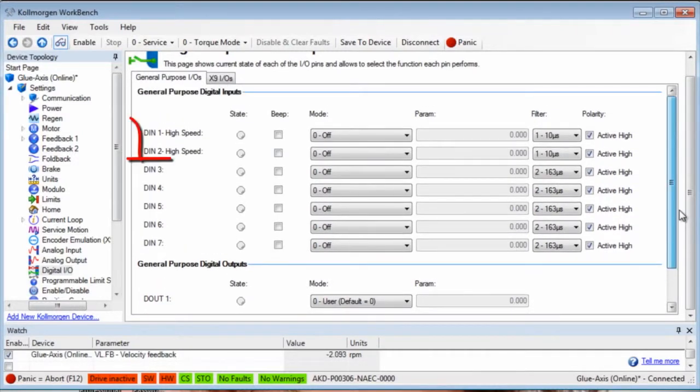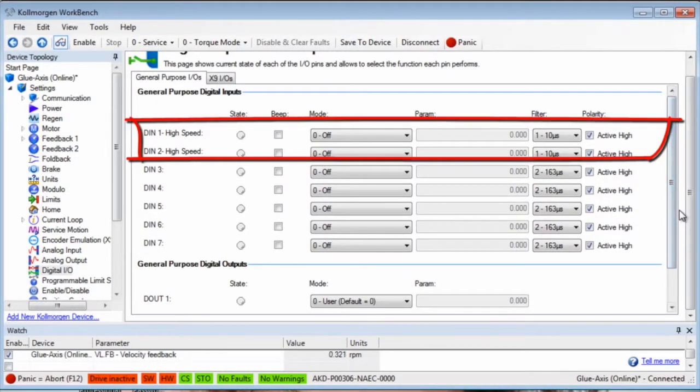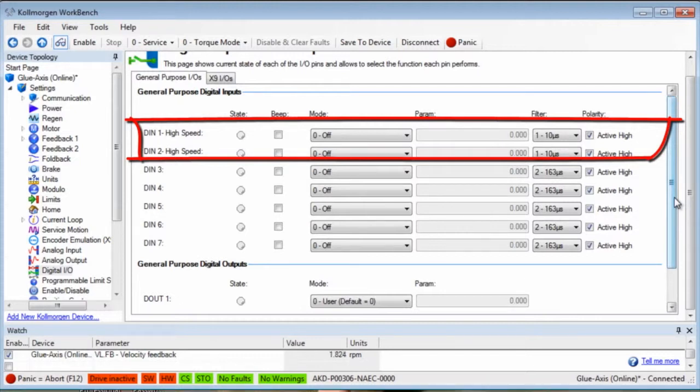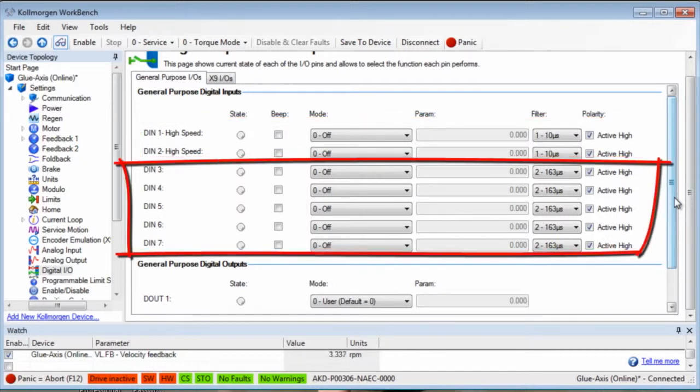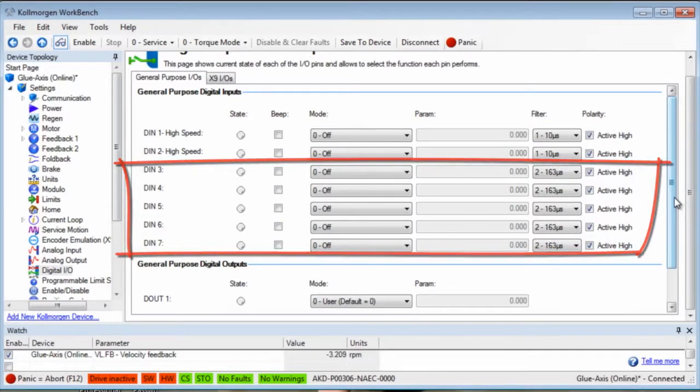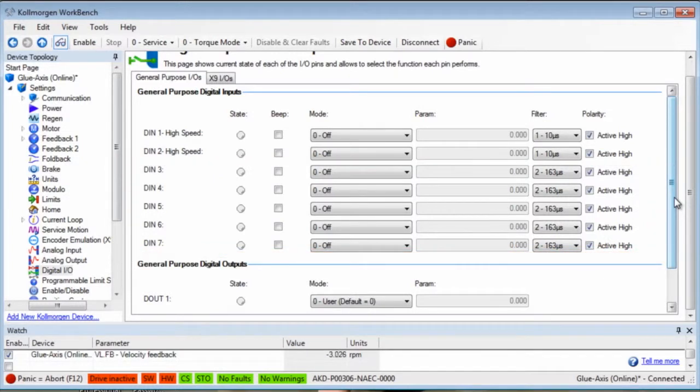Digital inputs 1 and 2 are high speed inputs that have an update rate of 2 microseconds. Because of their high speed, they are used for latching functions such as position capture. Digital inputs 3 to 7 are standard inputs with an update rate of 250 microseconds.